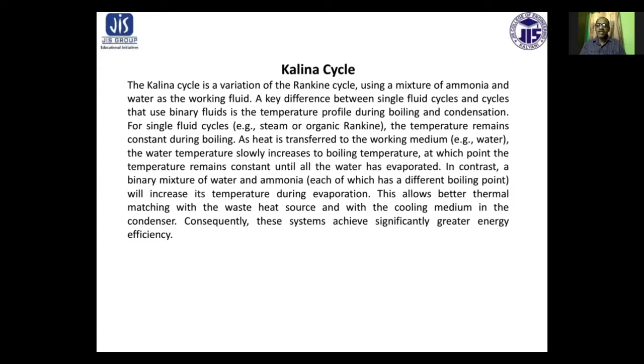In contrast, a binary mixture of water and ammonia, each of which has a different boiling point, increases its temperature during evaporation. This allows better thermal matching with the waste heat source and with the cooling media in the condenser. Consequently, this system achieves significantly greater energy efficiency.